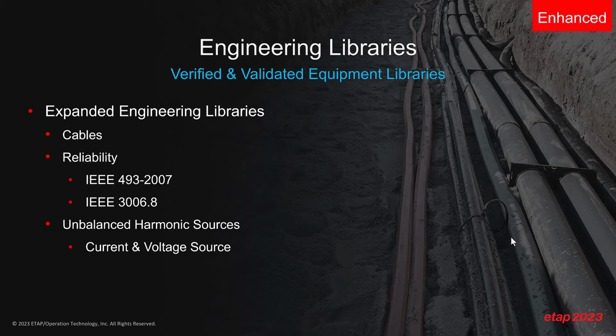The engineering libraries, which are our verified and validated equipment libraries, have also been expanded in this version to include even more cables, more reliability data, as I've discussed earlier, from 493 and 3006.8. And of course, with unbalanced harmonics, we've added new unbalanced harmonic sources that include current and voltage sources as well.